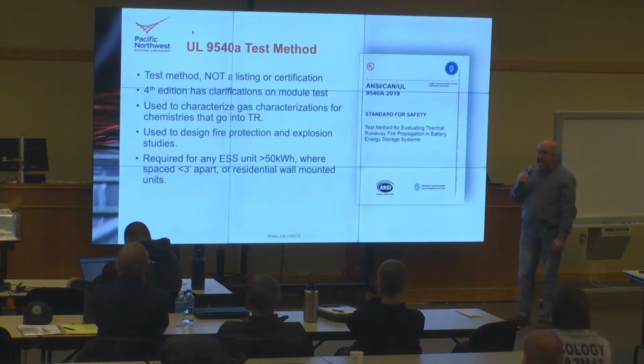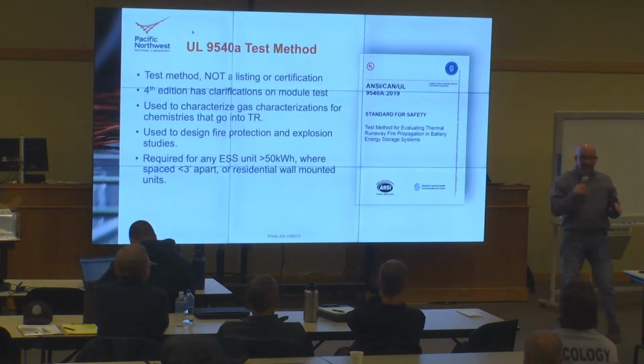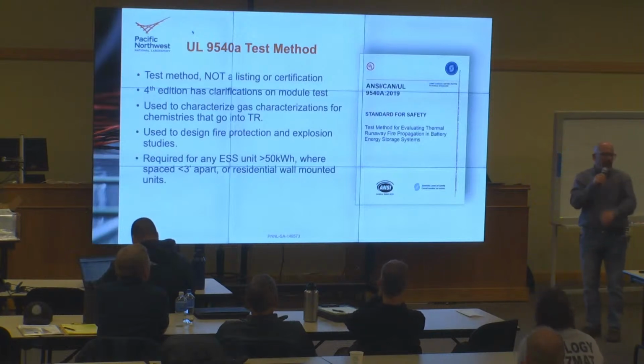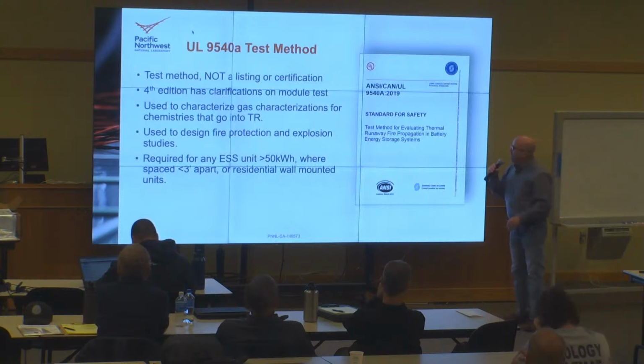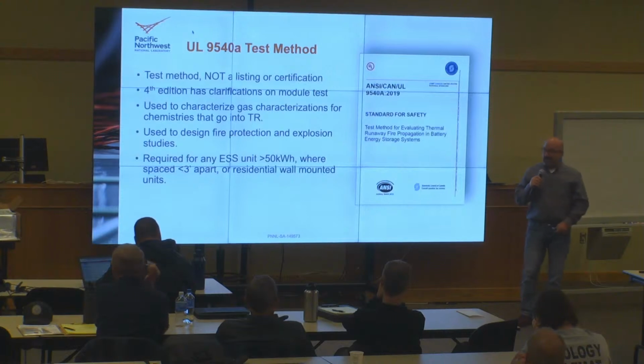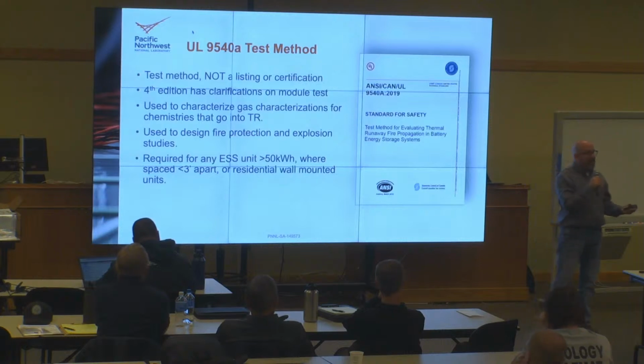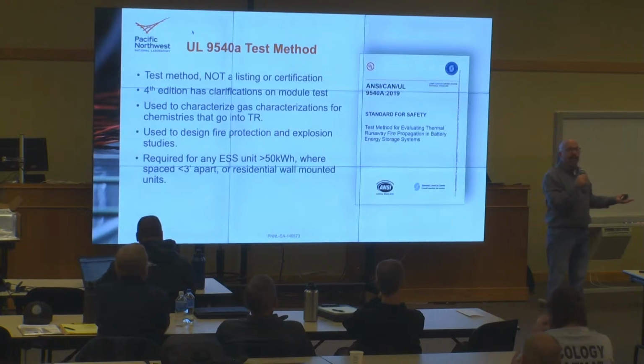This is not a listing or certification, not a pass-fail test. You'll see manufacturers say 9540A approved or certified to 9540A, and that's a misuse of what it is, which is why I want to see it go away. It's a standardized test used to give us data. It tells us how much it propagates and what kind of gases come out of it. Because explosion control is required, you need this fire test to know what gases you're designing for, so it's really critical.